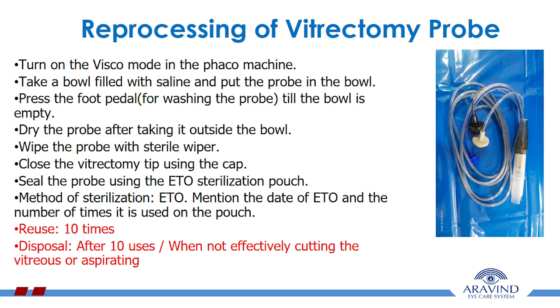Now we will see reprocessing of the vitrectomy probe. Turn on the visco mode in the phaco machine. Take a bowl filled with saline and put the probe in the bowl. Press the foot pedal for washing the probe till the bowl is empty. Dry the probe after taking it outside the bowl. Wipe the probe with a sterile wiper.